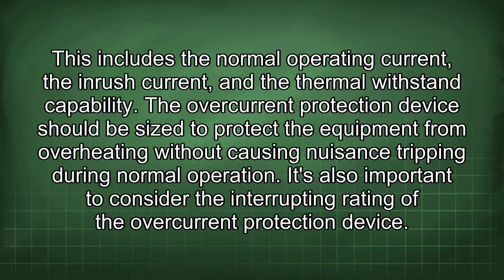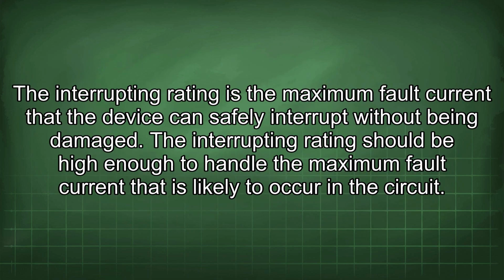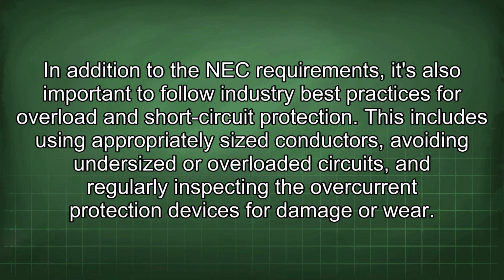It's also important to consider the interrupting rating of the overcurrent protection device. The interrupting rating is the maximum fault current that the device can safely interrupt without being damaged. The interrupting rating should be high enough to handle the maximum fault current that is likely to occur in the circuit. In addition to the NEC requirements, it's also important to follow industry best practices for overload and short-circuit protection.